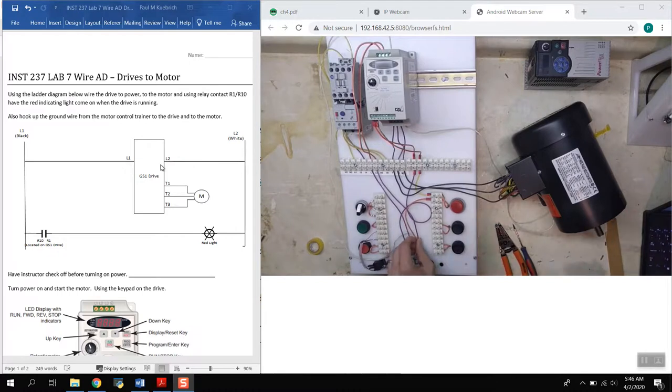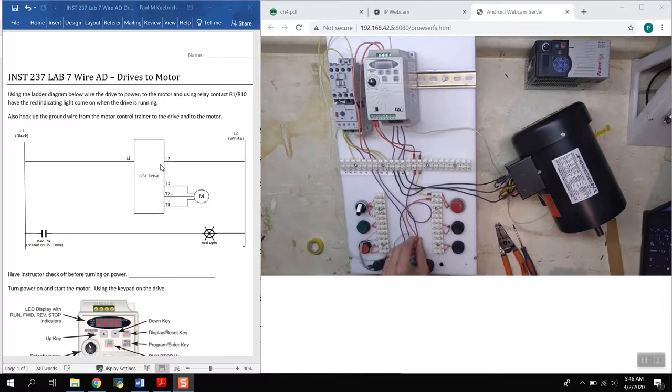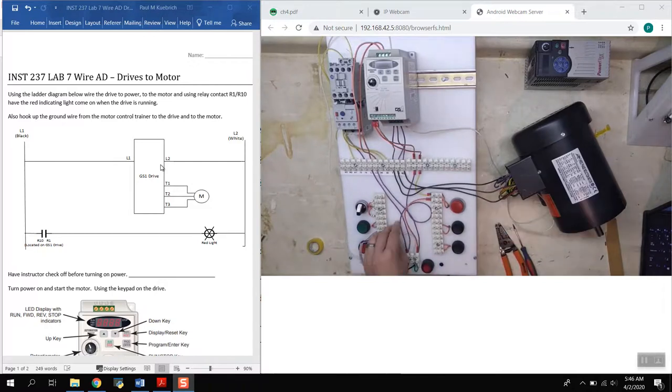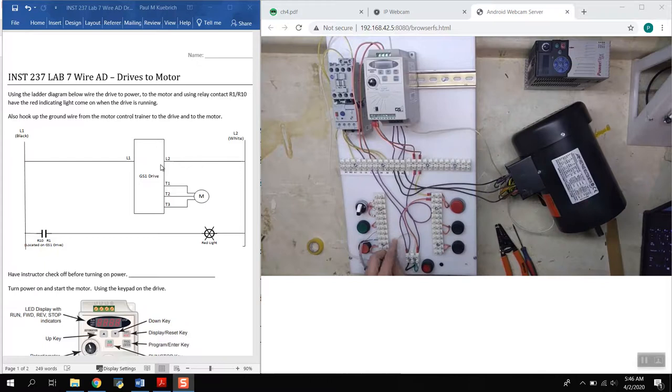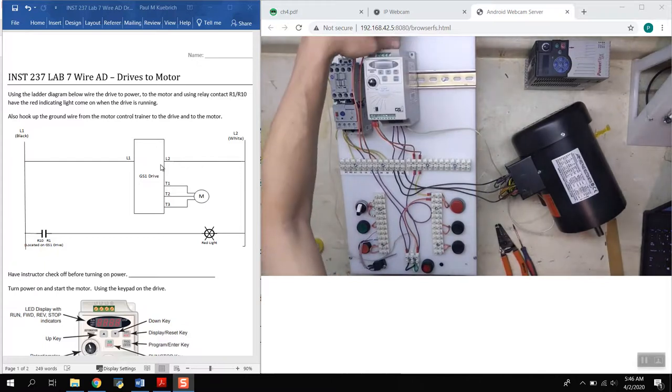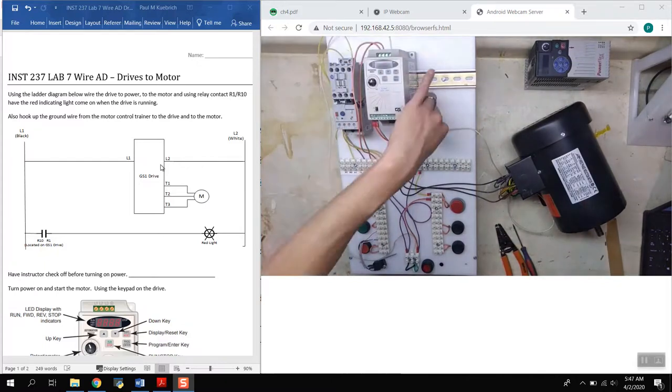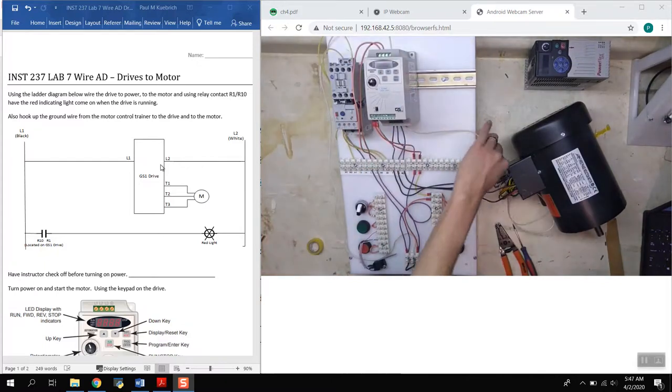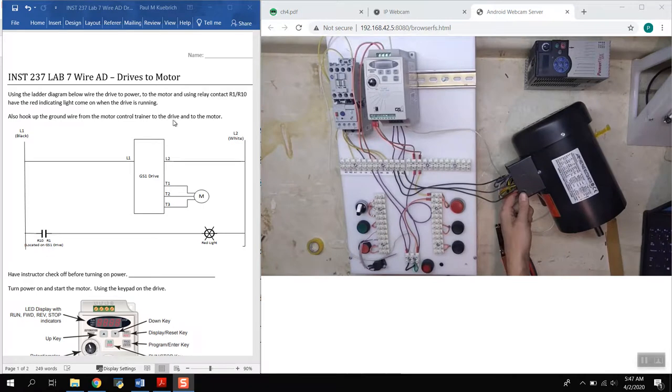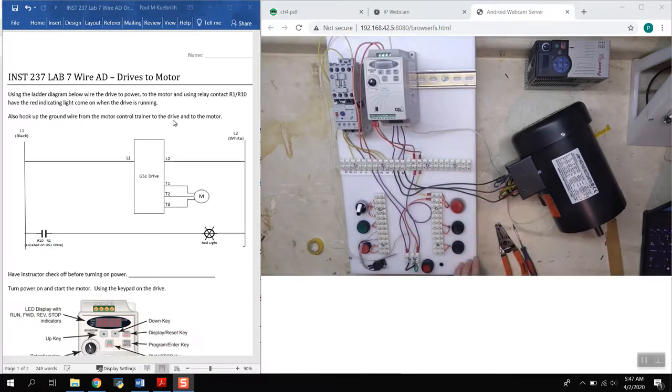Also not shown on ladder diagrams as you can see is they don't put grounding on there. Grounding is implied to be done. So here I don't have a green wire for it like I would like, so I use white instead, but ground comes in to the drive and from the drive into the motor, so everything is grounded as well.